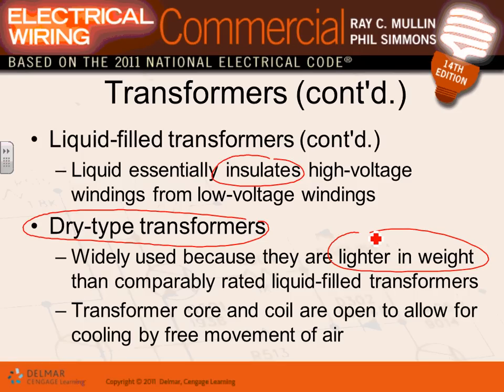So there are a whole lot of regulations related to putting a liquid-filled transformer inside your building. Most of the transformers that we put inside our buildings, guys, are dry type transformers because of fire hazard, and because they're light and they perform as well as liquid type for a smaller rating.